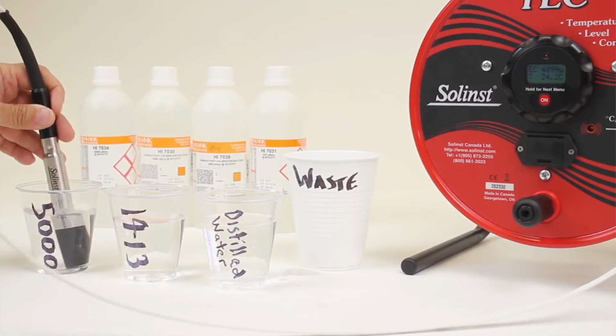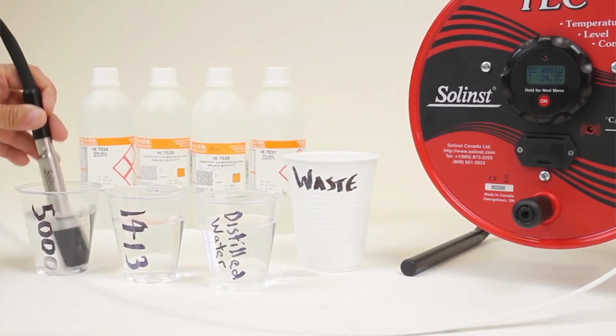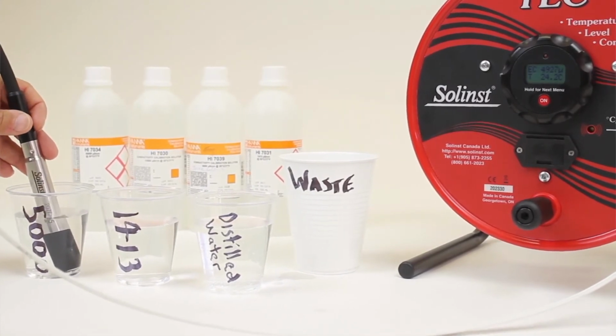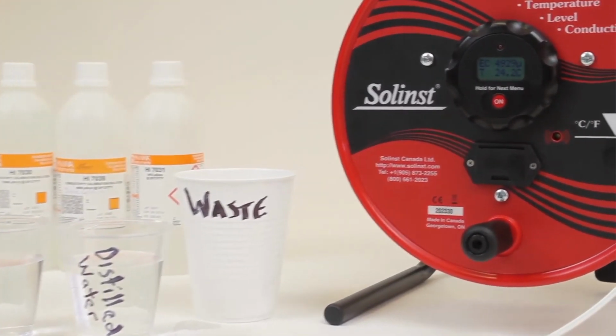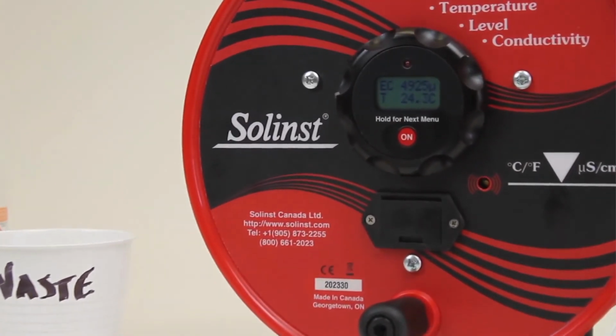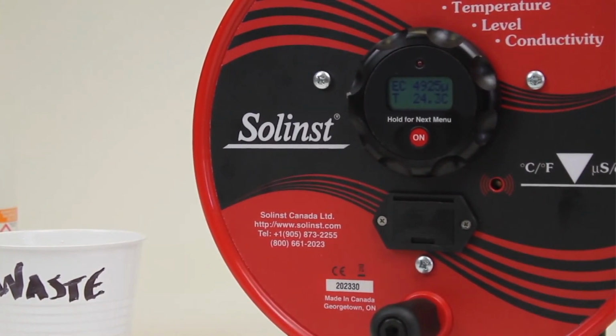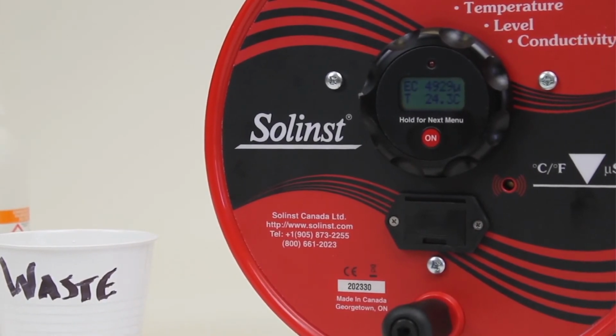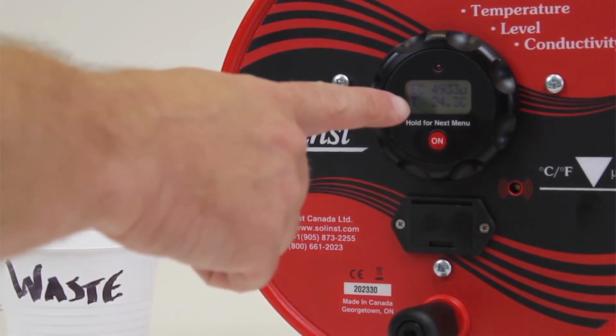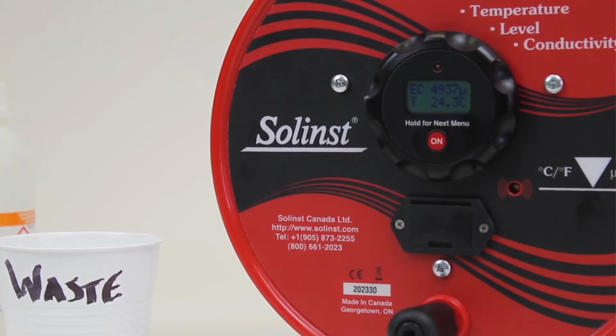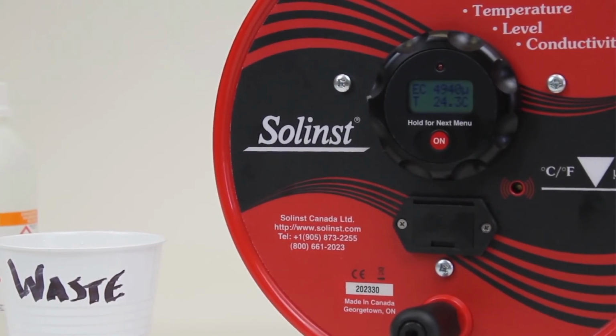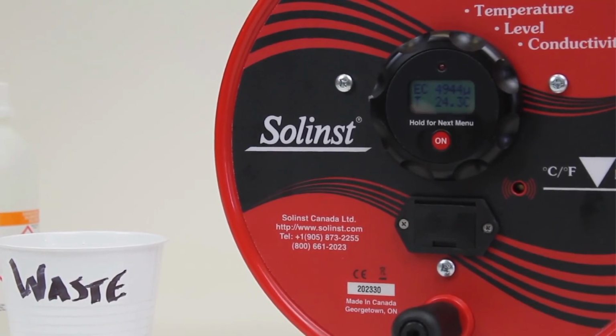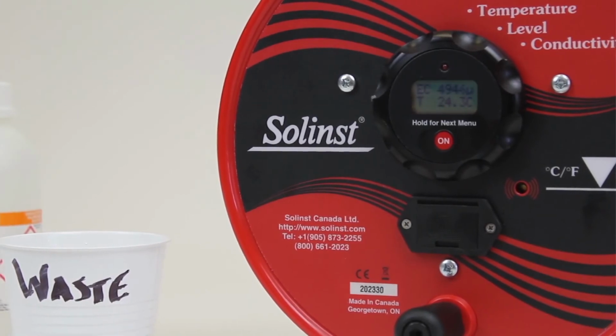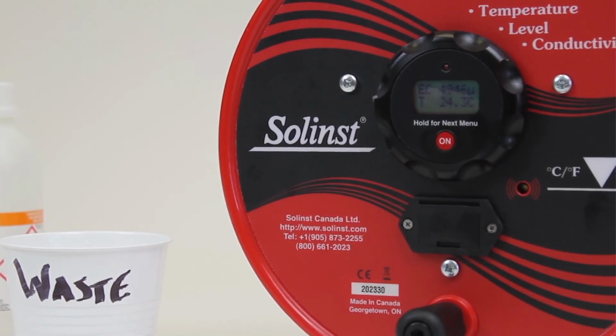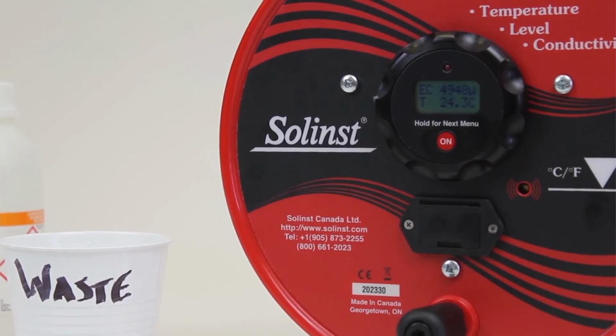I'm going a little bit faster than I normally would for a real proper user calibration. In a real life situation, again, you're going to take anywhere from 30 seconds to a couple of minutes to do this process for each calibration level. And now I'm ready to turn the unit on. I'm in 5000 solution. I take a look at the screen. It's 4,900. As long as I'm within 5% accuracy of the reading adjusted for temperature, I know I'm good. But even if it was beyond that, what I'm doing now is a user calibration which will adjust, bring it in closer to what it should be reading.